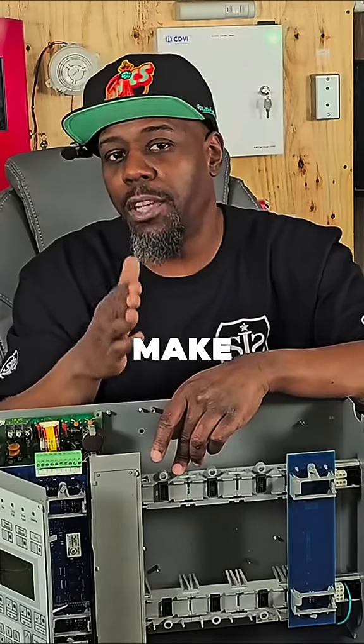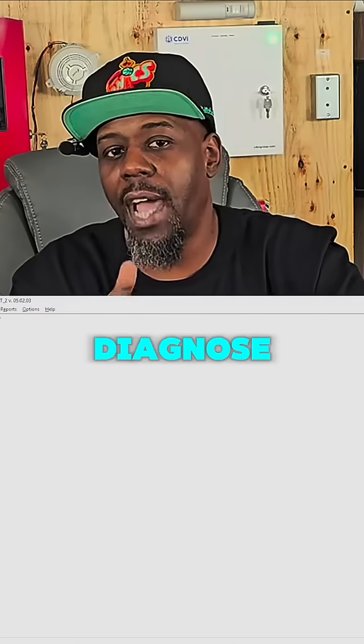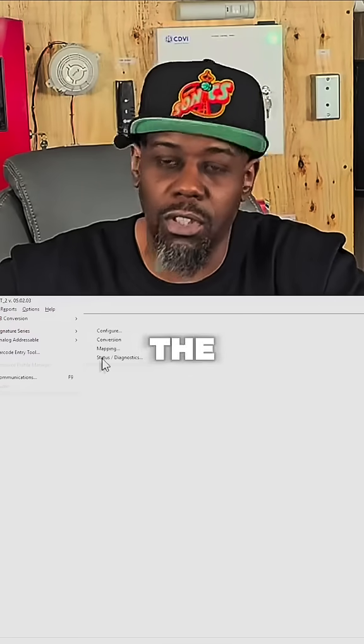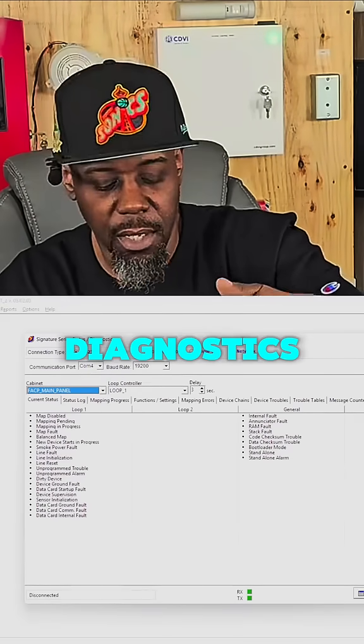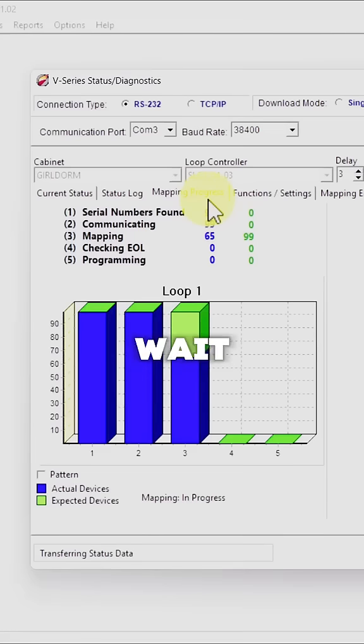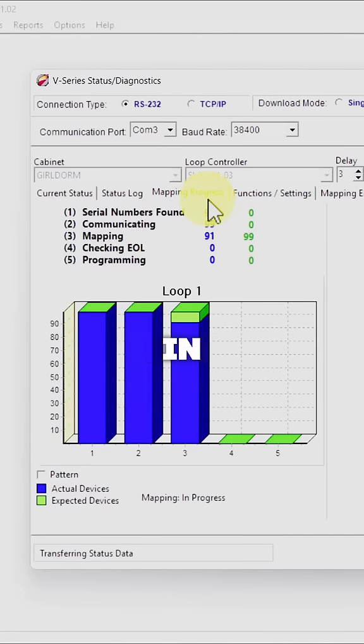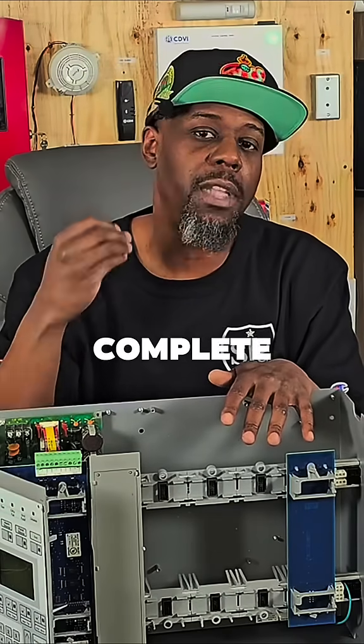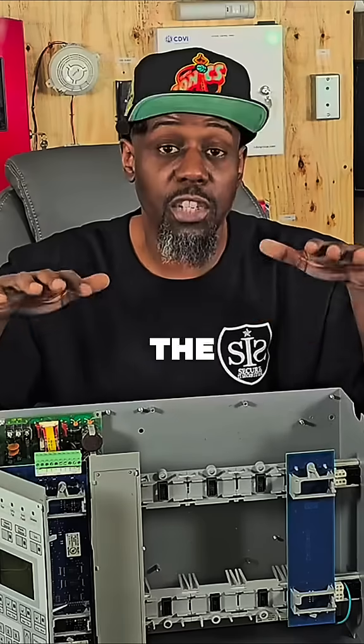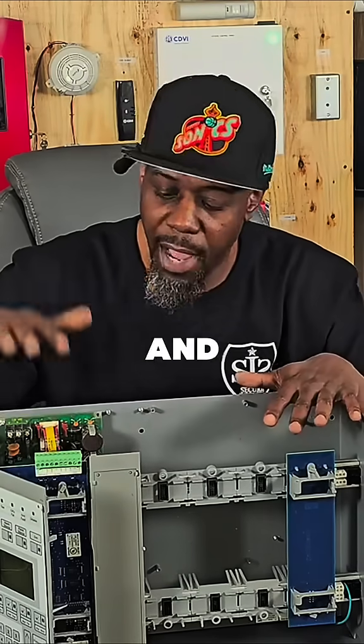Once you download to that, you want to make sure you diagnose your status. Don't run out the door at that point. Go to your status and diagnostics, connect to the loop card, and wait for the system to actually map all the way in and wait for the map to complete. Once the map is complete, you have one more step — you need to upload that complete map so that everything in the software and everything in the field is the same.